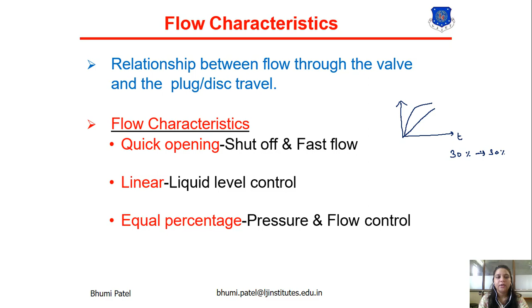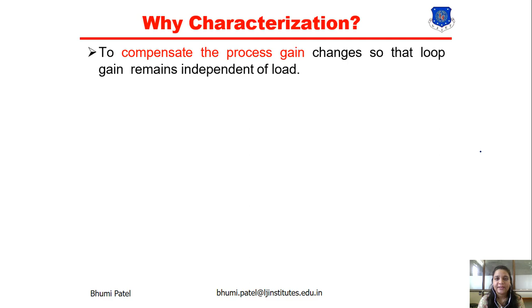So first of all, why is characterization required in the control valve? To compensate the process gain changes so that loop gain remains independent of the load. In the control valve, we always compensate the process gain changes, so characteristic is one of the most important parts of the control valve. Next is to provide uniform control loop stability over the expected range of operation. In the field, we can use the control valve in different areas and different instruments, and after all we can find the stability of the system. So using the characteristic graph, we can provide uniform control loop stability.